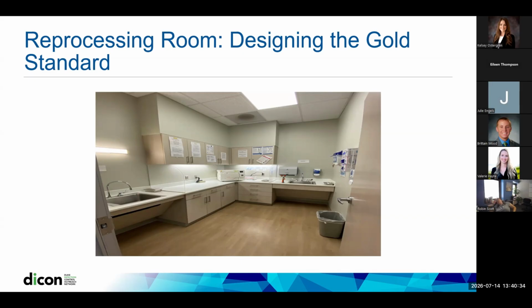So there's an example of what we think is an ideal reprocessing room, and it moves from dirty to clean quite nicely. On the left, we start with a dirty or manual cleaning sink. It's separated by a splash guard, so we get to retain all of the use of the counter space to the right of that, where instruments are laid out to dry and inspected. They're put in the autoclave. There's a nice place for sequestering instruments before the BI is read out, and documentation. And then our clean hand washing sink is also separated by a permanent splash guard to prevent any water contamination to the left of that sink.